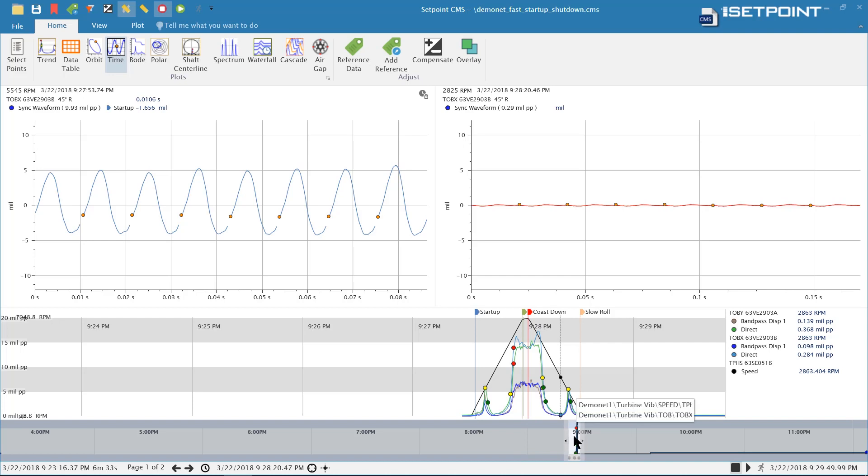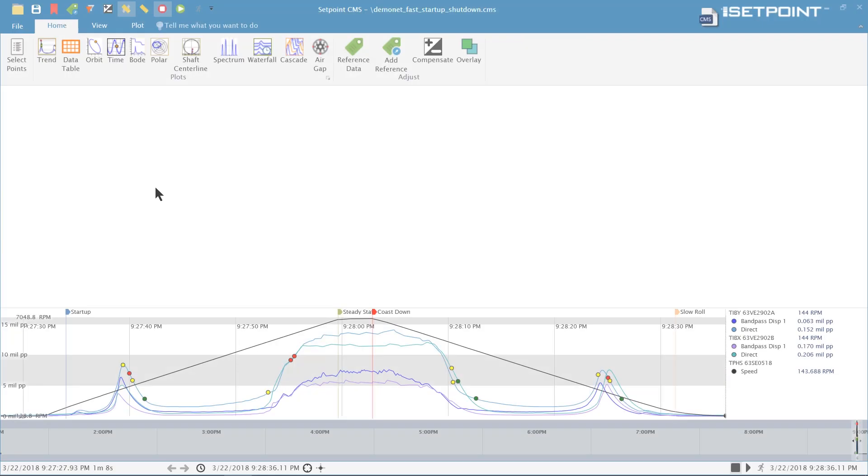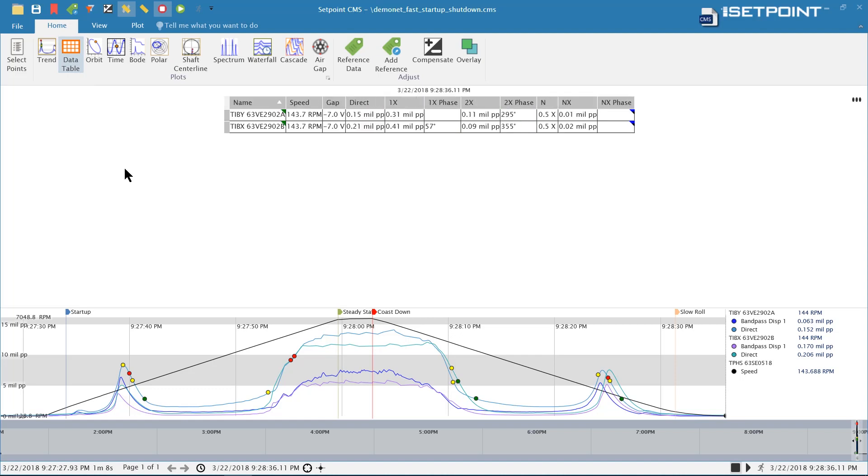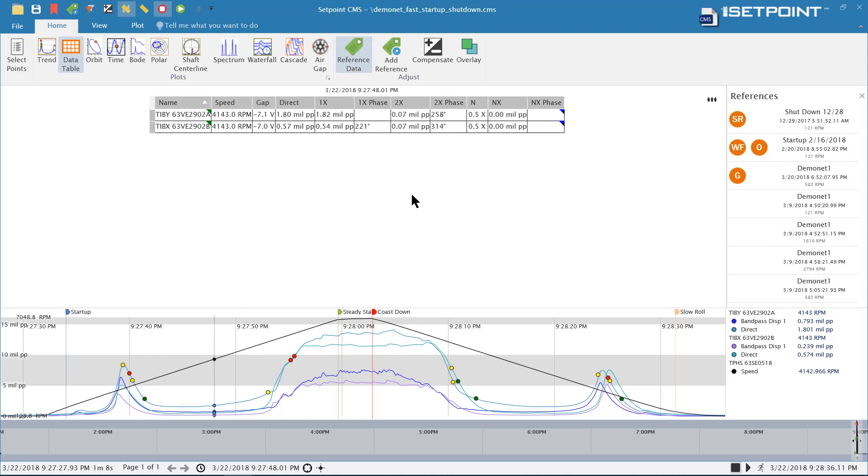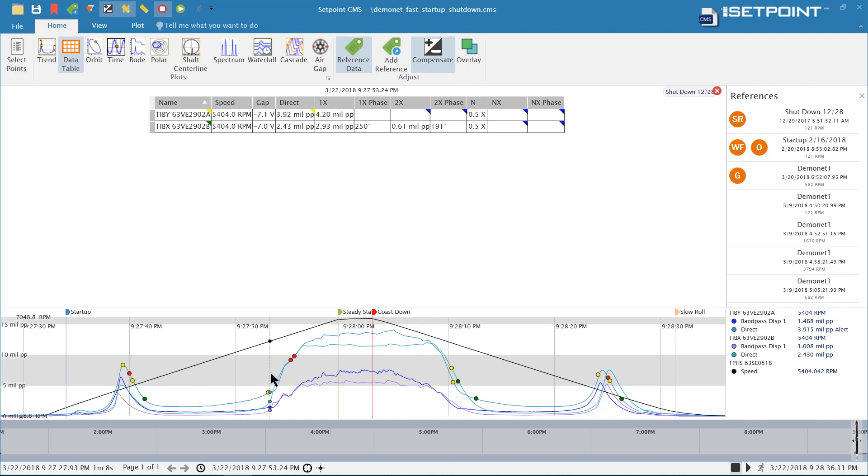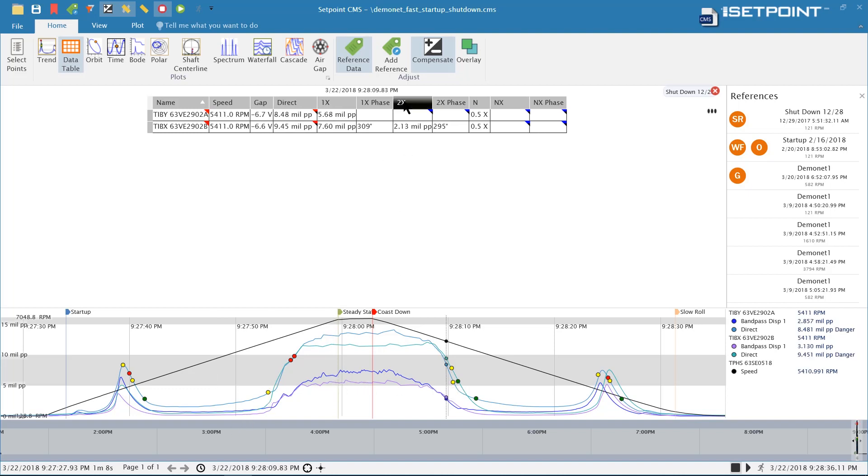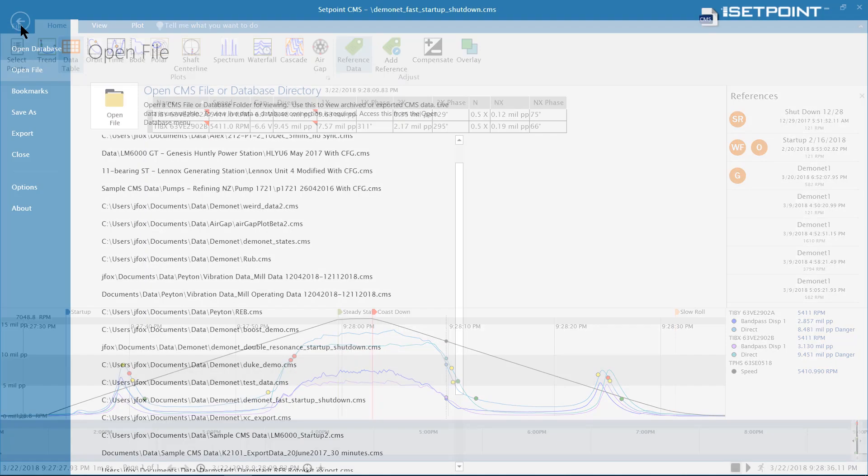Another feature we've added to the new version of Setpoint is the ability to compensate data on the data table. We've always had compensation for other transient plots like the bode and the polar, but we've now added it to the data table so you can compensate the individual values that are showing up. Here I have uncompensated data, but let's turn on compensation for this data set. When I do that, the slow roll vectors get removed from the data and now we can see the compensated data in the trend.